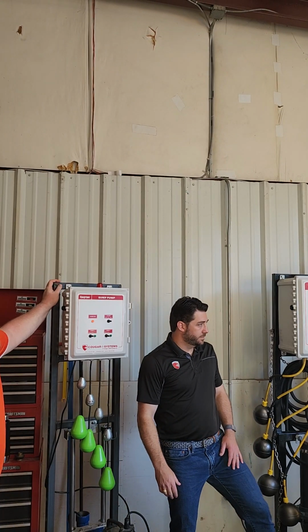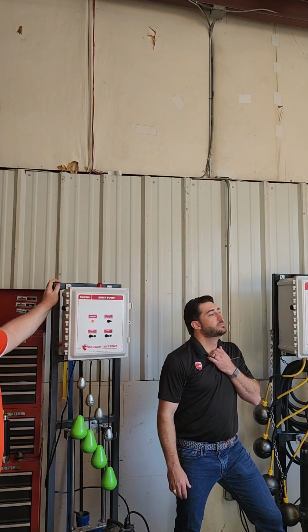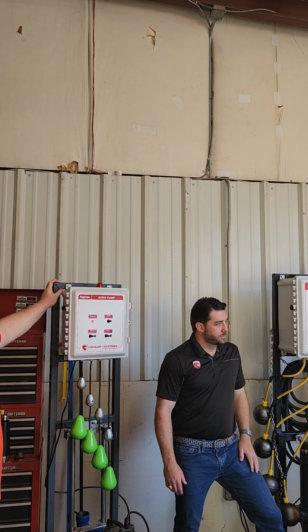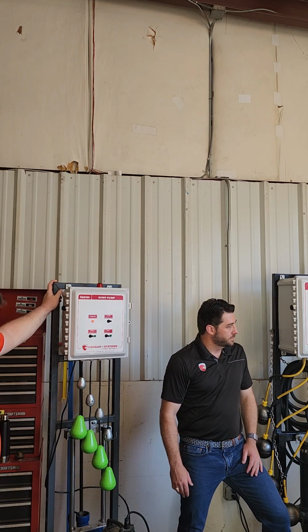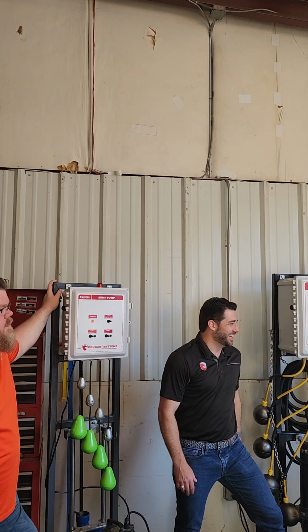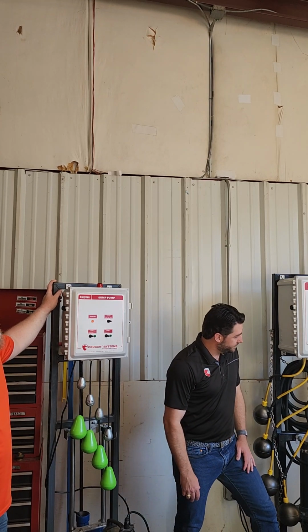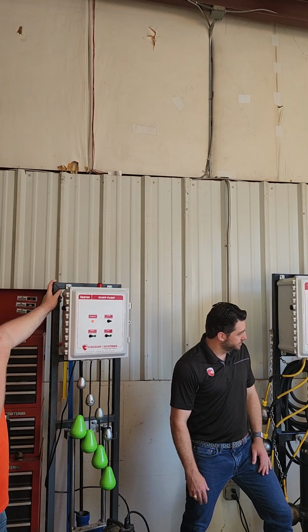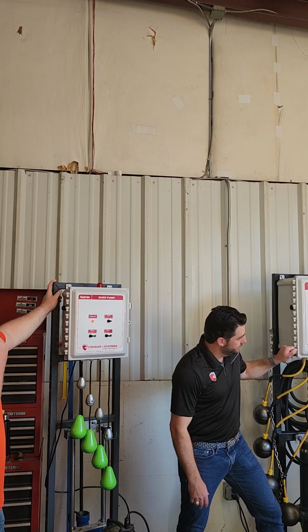No. That second pump's always just the emergency, like, oh crap. Yes. Something happened to the first one. Yeah. So whenever you show up, it's like, how did both pumps fail at the same time? Yeah, correct. They never failed at the same time. The problem is it's always been working on the second pump. Nobody knew about the first one that locked up. Yeah. Now you show up and they're both locked up.